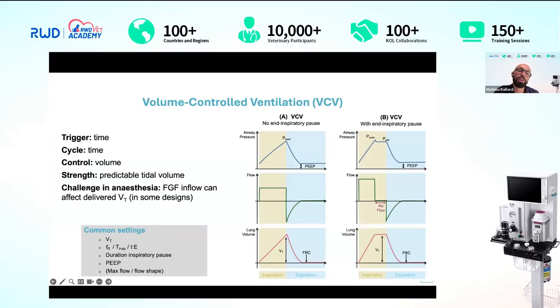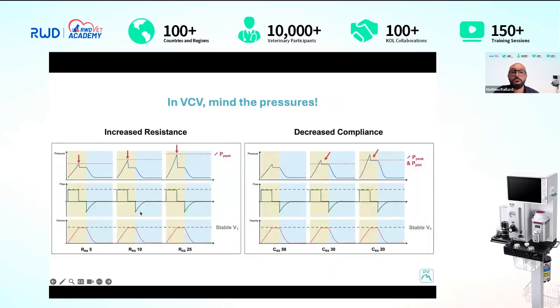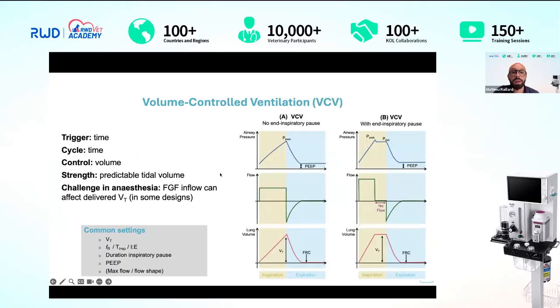I also have the option of setting an inspiratory pause. So if I want, I can actually have a flow that is a little bit higher for a time that is shorter than the inspiration and have, despite being still in inspiration, a time of no flow. In that case, the tidal volume will be reached faster. So that's what happens here. You see in inspiration, if I have my insufflation in volume control ventilation throughout the duration of the inspiration, I have a square wave and the insufflation happens throughout the inspiration. If I have an end inspiratory pause, I have a flow that is a little bit higher for a similar tidal volume, but then I have a little period of no flow.